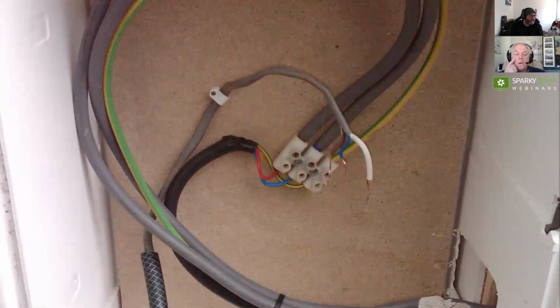But these new mobile homes these days come with fully loaded boards, and as we can see, 16 mil or 25 mil tails going onto the end of your 2.5 mil armoured cable. So when you look at this initially, you think, goodness me, the size of those tails and the size of the armoured, there's something wrong there. Well actually, the armoured was perfectly okay for the size of the circuit breaker, the overcurrent protection behind it.